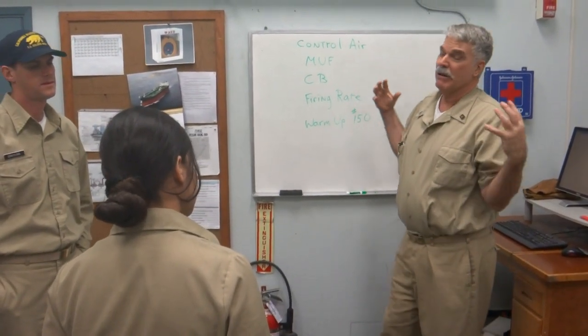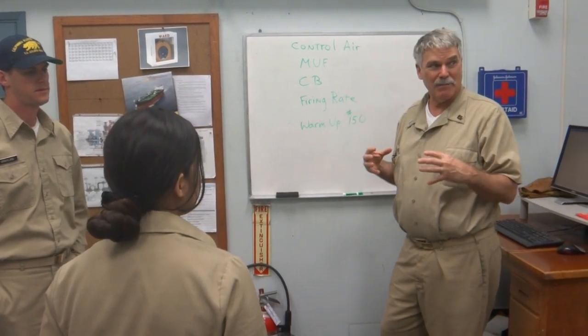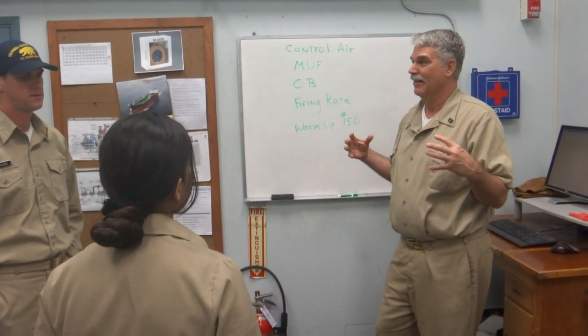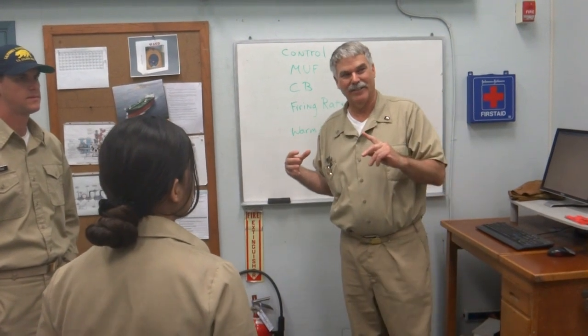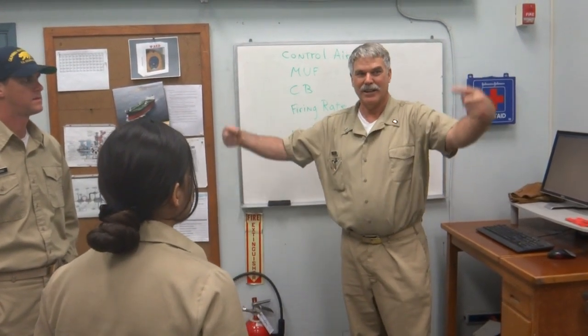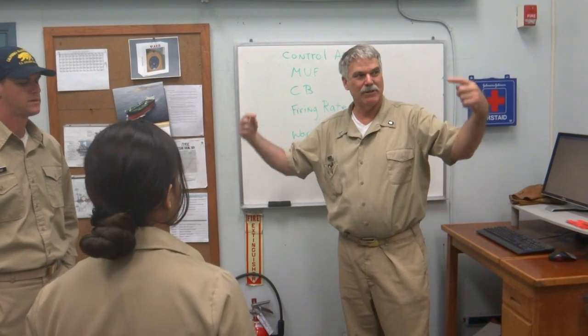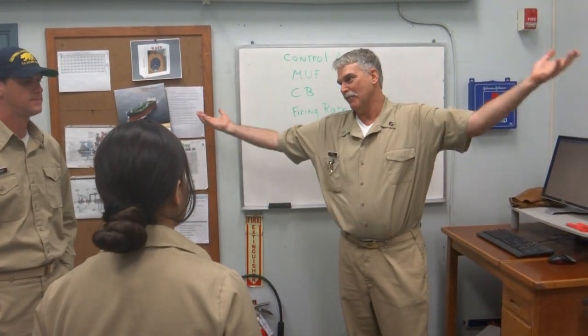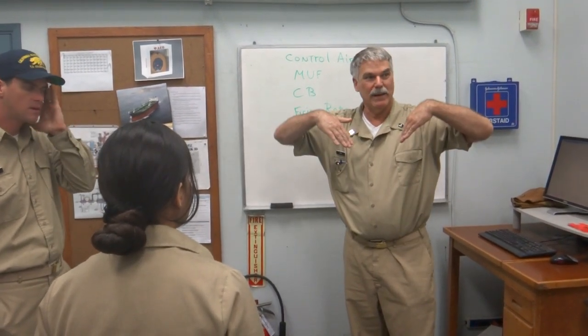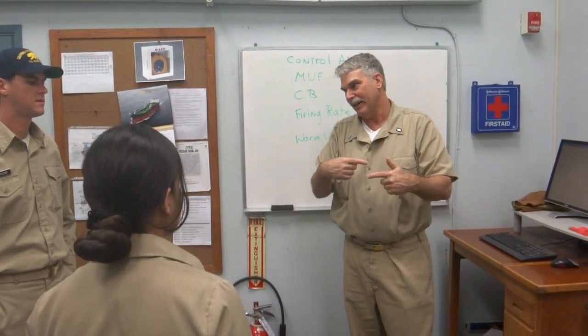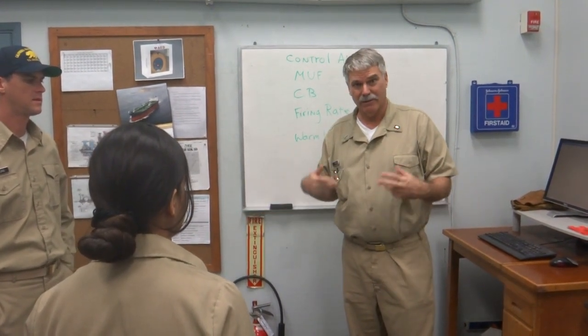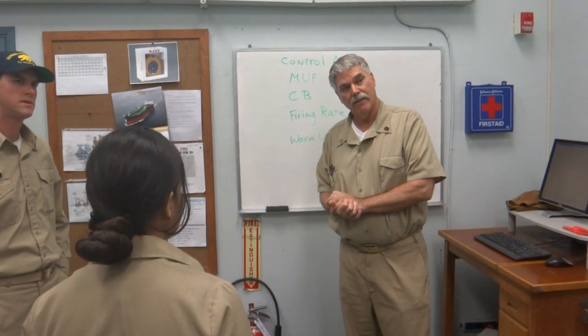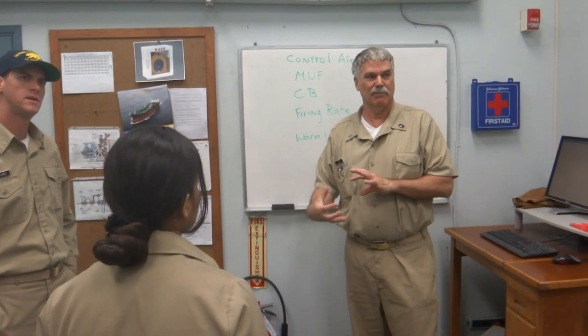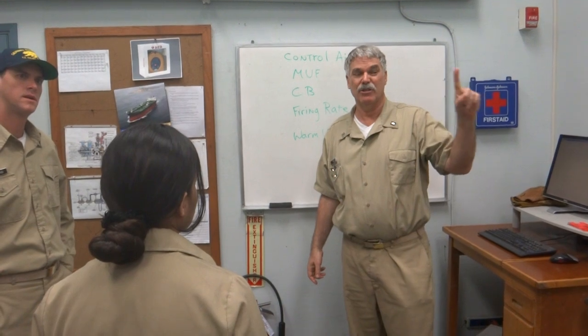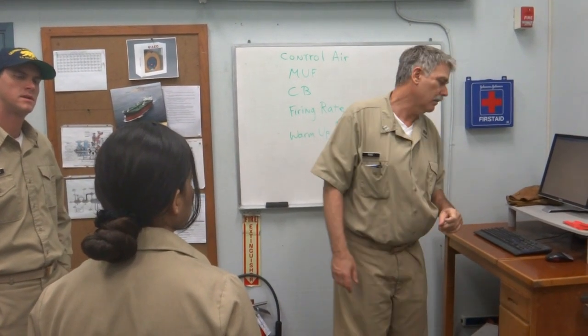But before you can put gland seal on the turbine, what do you have to have? Lube oil. What else do you have to have? Air? Jacking gear. You have to keep rotating it because that hot steam is only supported on either end with a bearing and a heavy wheel in between. So it's going to be turning, which means you're going to have lube oil. Those two things you've got to have. And the jacking gear is like an electric. Yeah, it is a small motor. It's like 6 revolutions an hour. Very slow. I mean, on the screw.